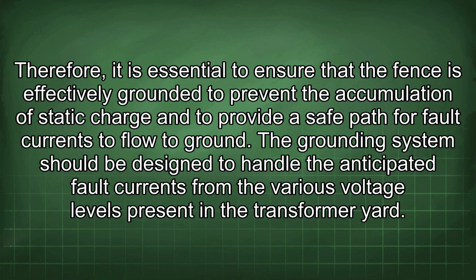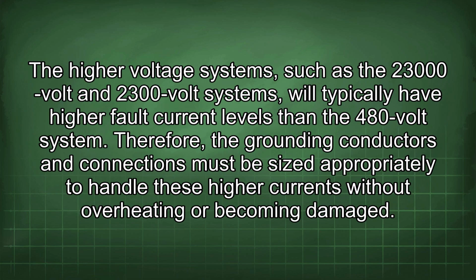The grounding system should be designed to handle the anticipated fault currents from the various voltage levels present in the transformer yard. The higher voltage systems, such as the 23,000 volt and 2300 volt systems, will typically have higher fault current levels than the 480-volt system. Therefore, the grounding conductors and connections must be sized appropriately to handle these higher currents without overheating or becoming damaged.